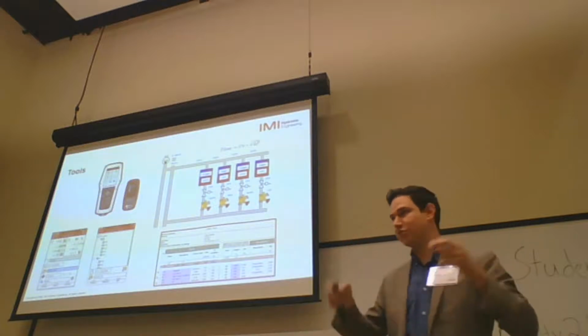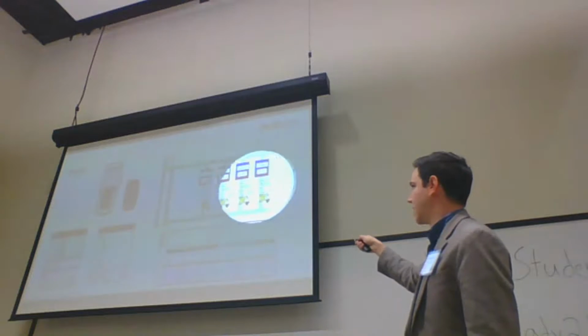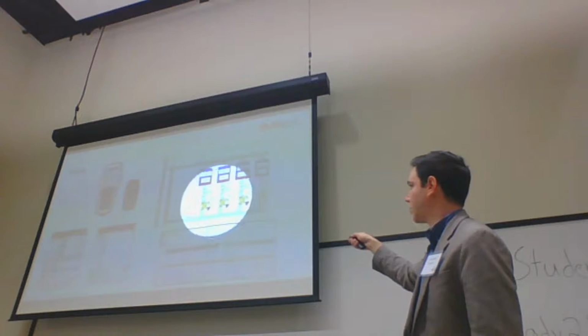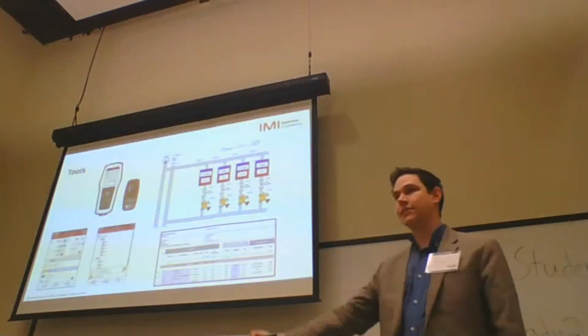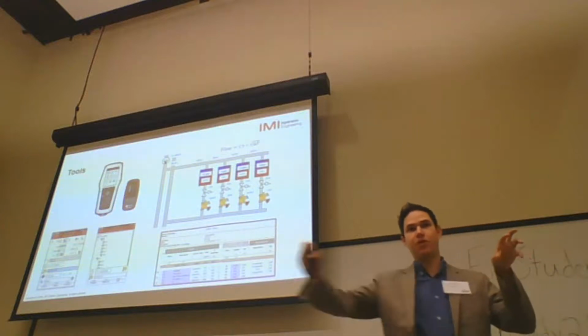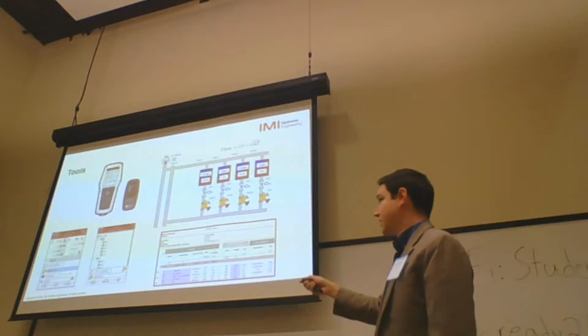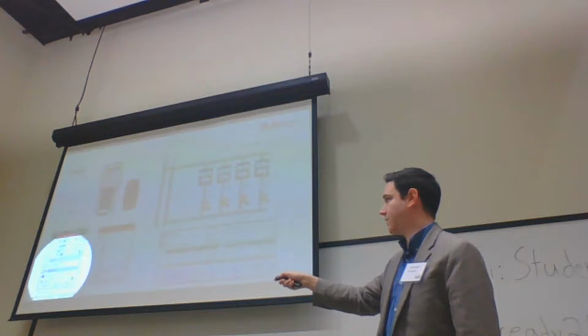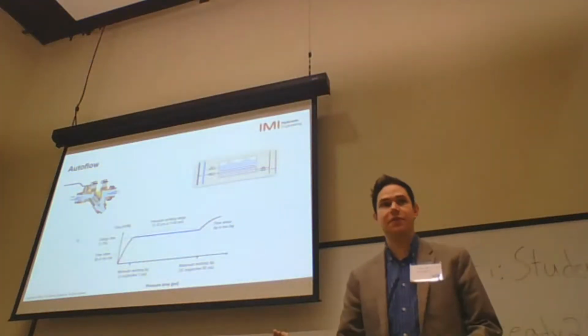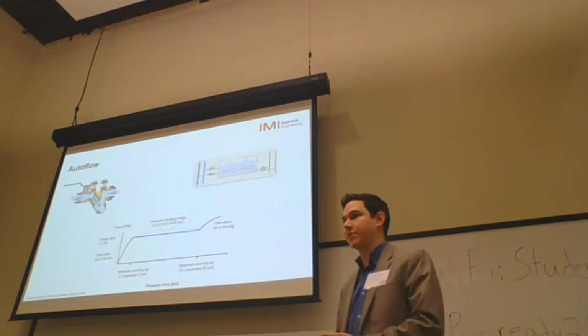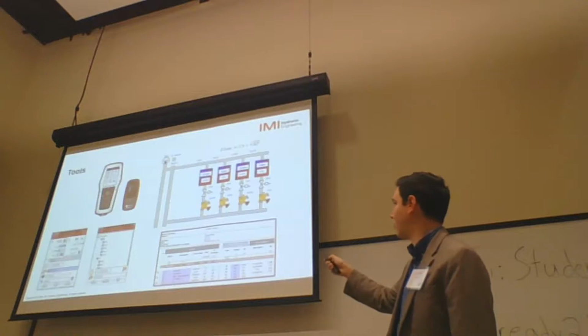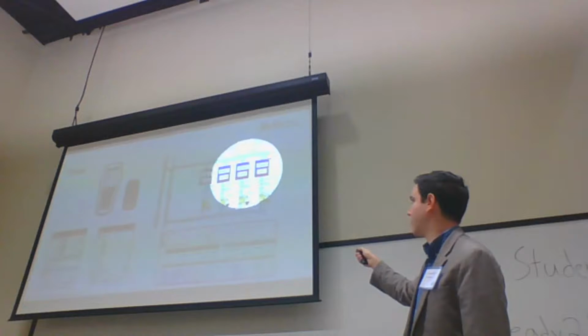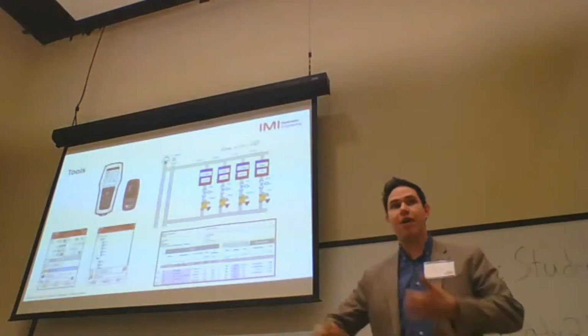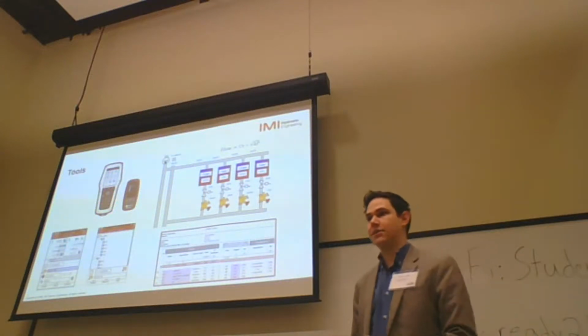So the wireless methodology in that case is always starting from the back and setting these 2 devices right there at the same percentage. And when you go to the one before and you set it to the same percentage as the last one again, the 3 balancing valves will have exactly the same percentage as well, because everything that you move upstream will move at the same percentage-wise. So this is the logic behind the software to use this calculation right there. So you see that the biggest numbers that we have are not the flow rate, but just a percentage. It doesn't matter if it's the same flow rate, what matters is if it is the same percentage. So even if the last coil is 2 GPMs, or sorry, 5 GPMs and this one is 2.5 GPMs, we always look at a percentage, not at the flow rate, to use this balancing method.